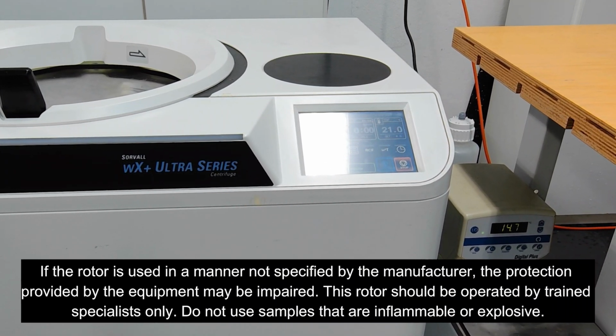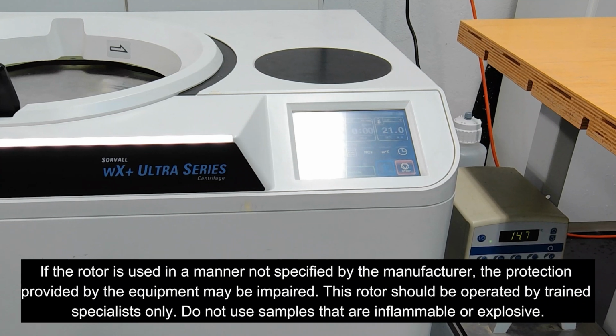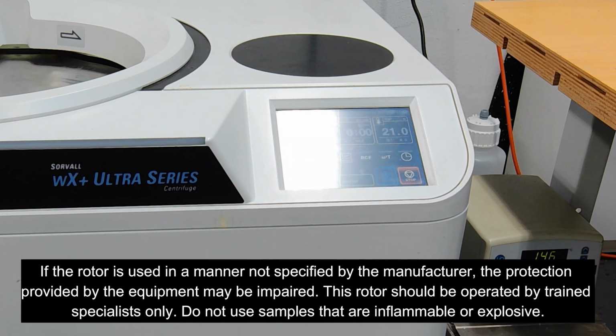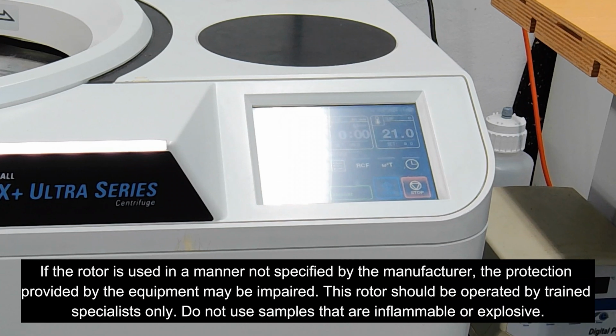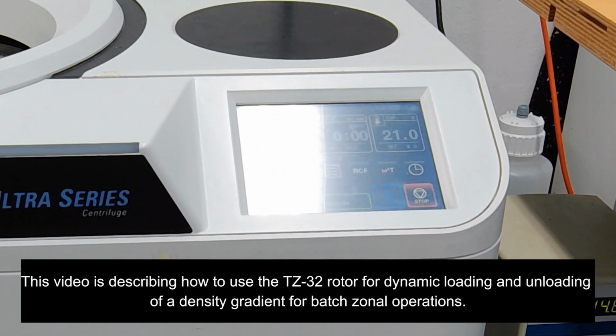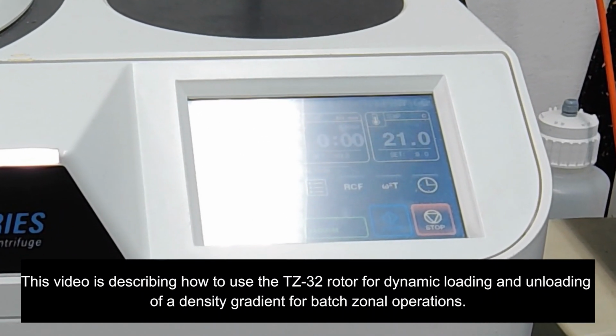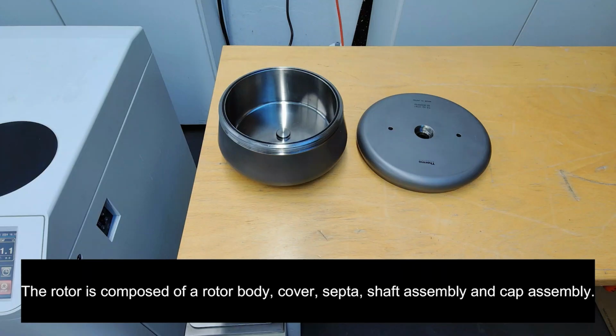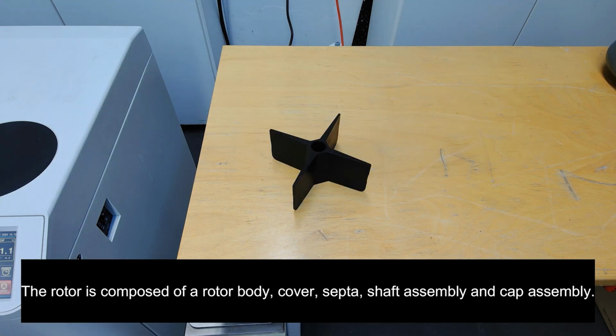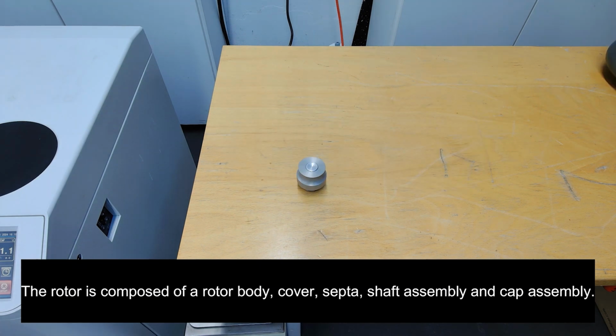If the rotor is used in a manner not specified by the manufacturer, the protection provided by the equipment may be impaired. This rotor should be operated by trained specialists only. Do not use samples that are inflammable or explosive. This video is describing how to use the TZ-32 rotor for dynamic loading and unloading of a density gradient for batch zonal operations. The rotor is composed of a rotor body, cover, septa, shaft assembly, and cap assembly.